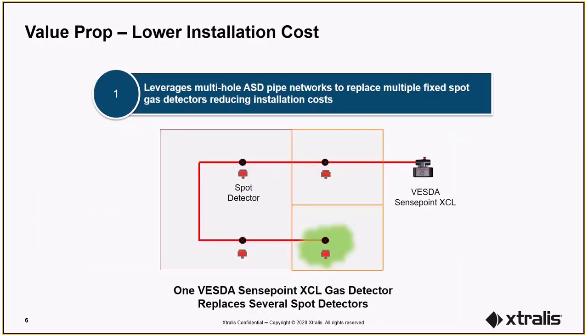VESDA Sensepoint XCL supports multi-point gas detection. In this example, we can see how, by using one VESDA Sensepoint XCL detector, additional sampling points can be added to increase the sampling point density in a large single space or to protect a number of compartmentalized spaces. The end result is lower installation cost compared to a system that will require multiple spot gas detectors.